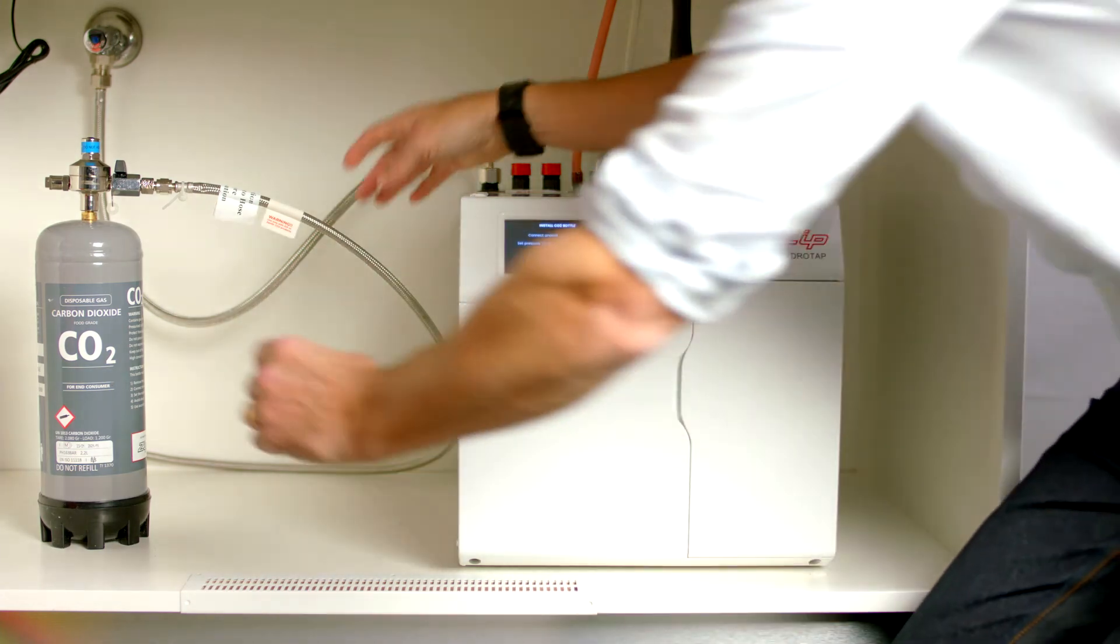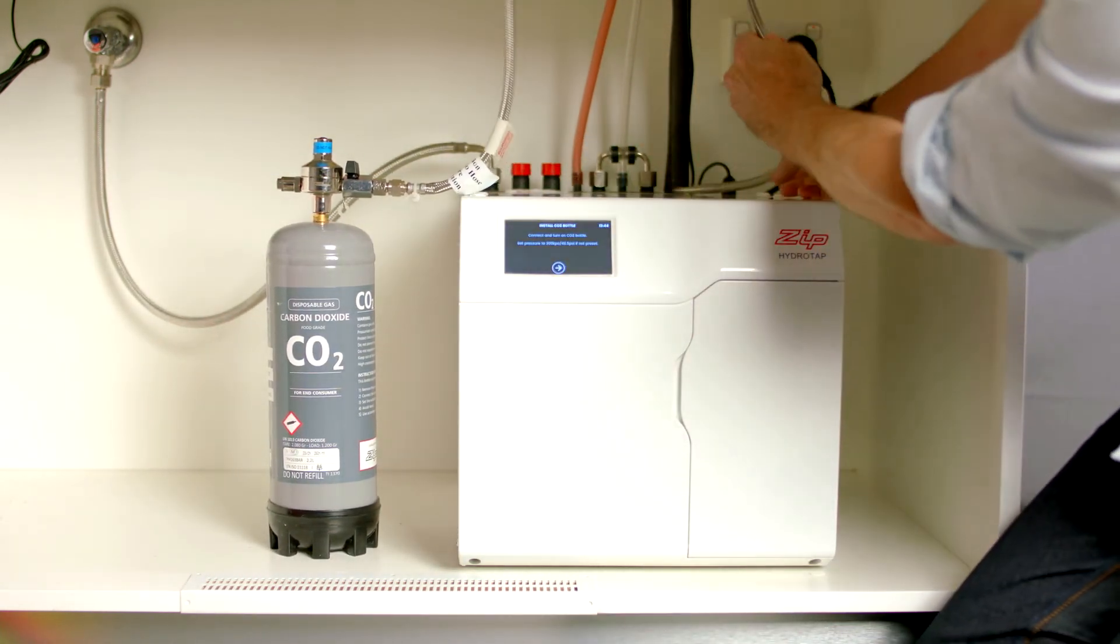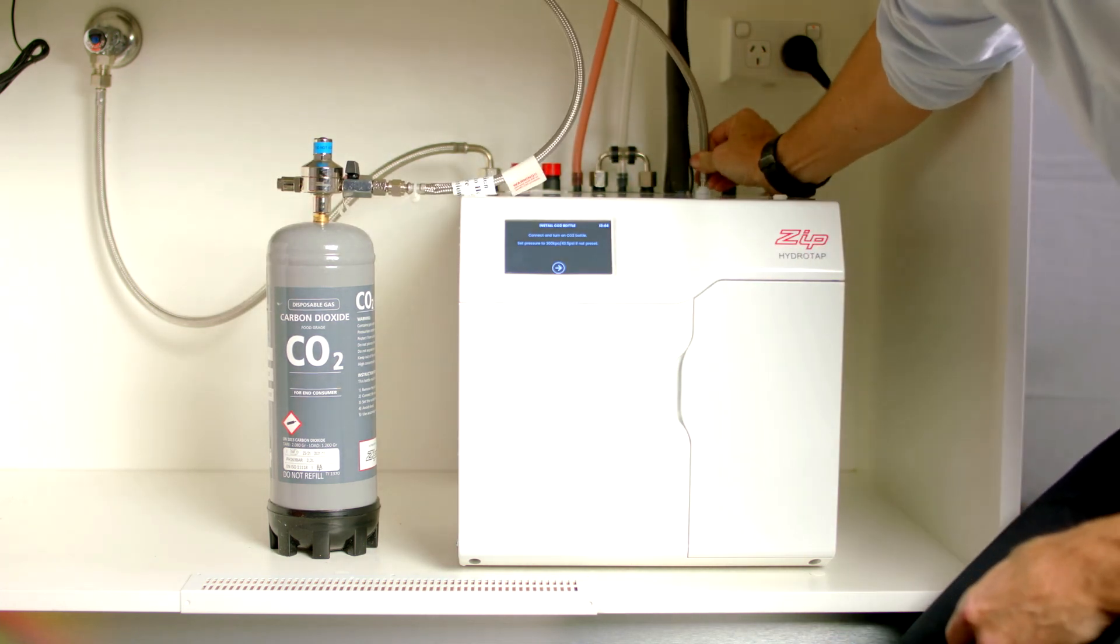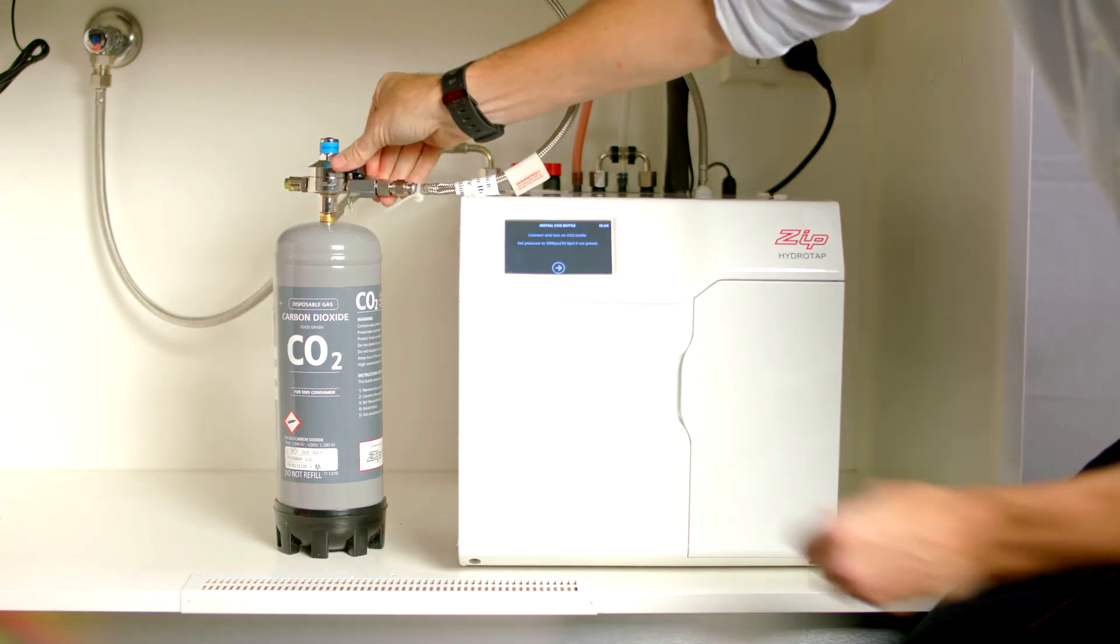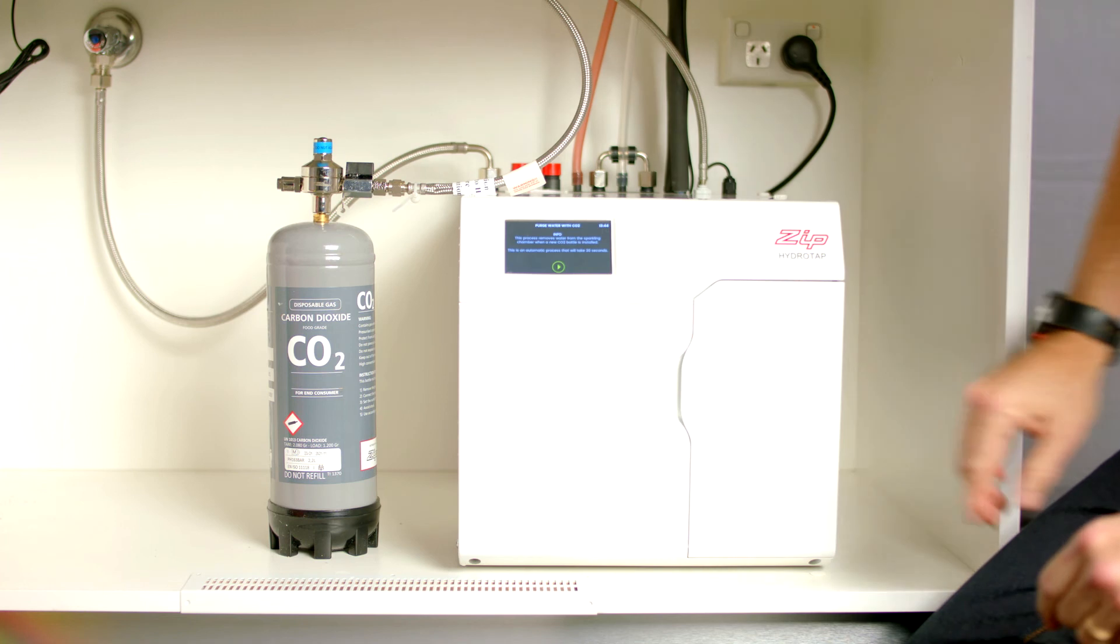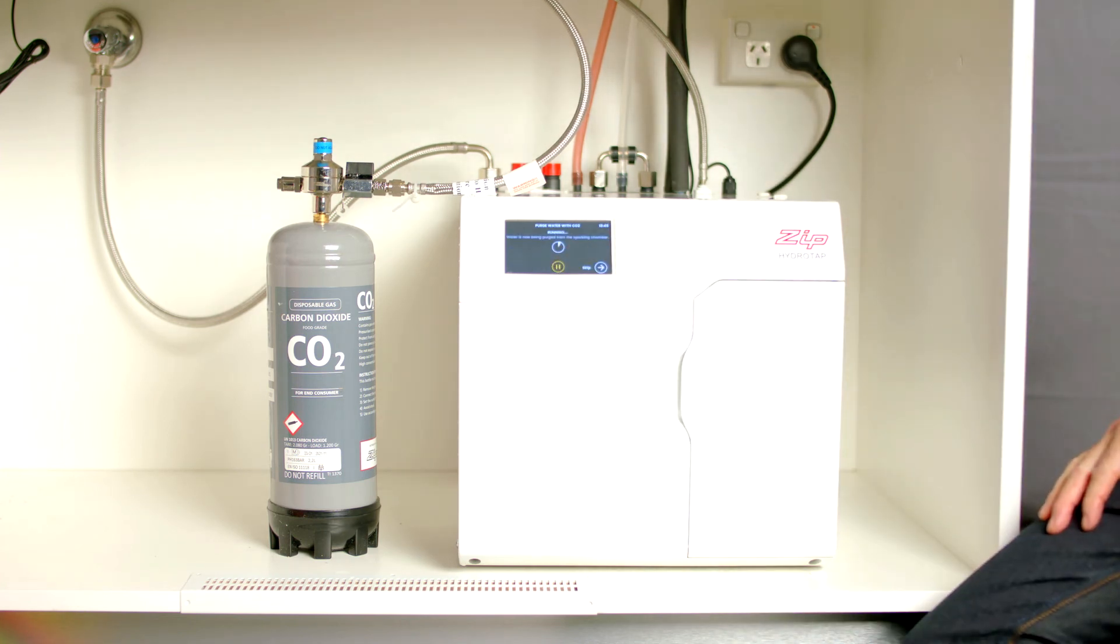Once complete the screen will ask you to connect and turn on the CO2 bottle. If you have a preset regulator turn the regulator fully on. If you need to set the pressure of the CO2 set it to 300 kPa or 43 psi. Once connected press the play button to start the CO2 purge which will take 30 seconds.